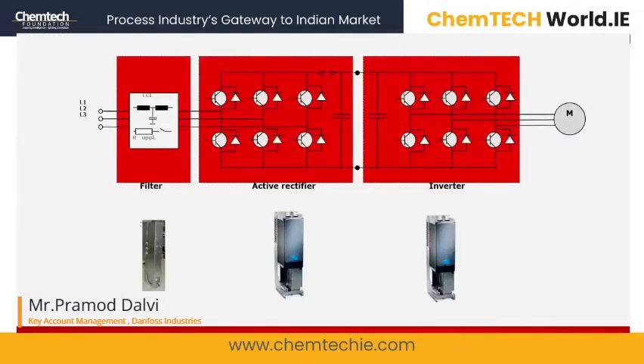This is a configuration where the active front-end drives come in. There we have three major components: the filter, the active rectifier, and the inverter. The active filter, active rectifier, and inverter are all IGBT based. And if it is a normal 6-pulse drive, then the rectifier is either diode based or diode plus thyristor based.